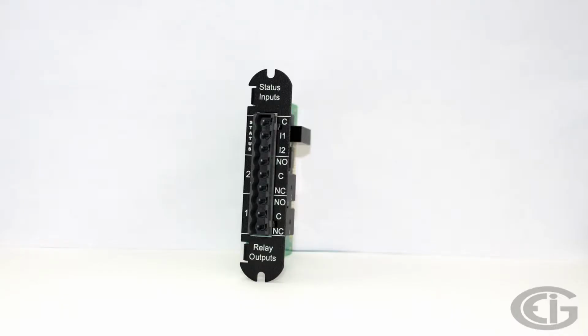The first card has two relay outputs and two status inputs. We can drive the relay outputs with limit conditions we set in the profile for the Shark 200. For example, we could monitor power factor and trip a relay to switch in a capacitive load bank when the power factor reaches a predetermined value. We can use the status inputs to check the state of an external device.